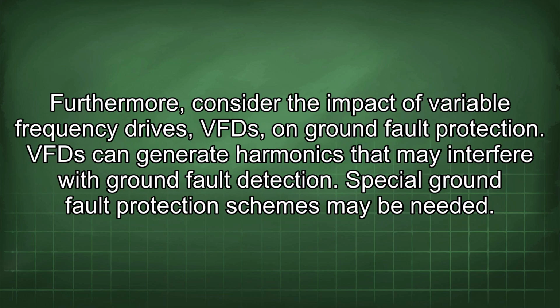Furthermore, consider the impact of variable frequency drives, VFDs, on ground fault protection. VFDs can generate harmonics that may interfere with ground fault detection. Special ground fault protection schemes may be needed.